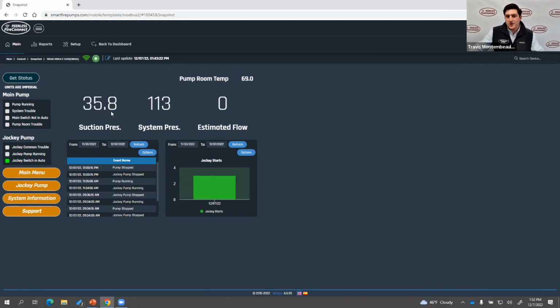So we give you suction pressure and system pressure. We load in your pump curve, and based on the difference of what's happening here, if the pump is running, so we log that pump running signal from that dry contact. So when that pump turns on, we get that signal. We can plot against your factory curve or your annual flow test curve what that difference in pressure is, and give you a flow estimate here.